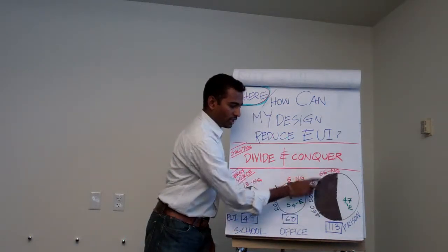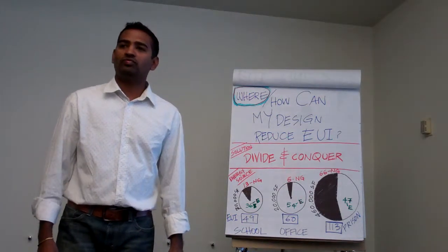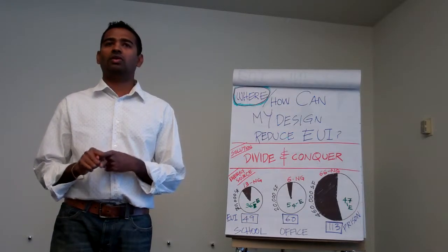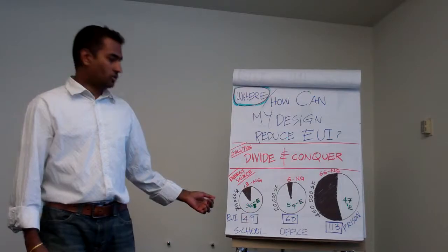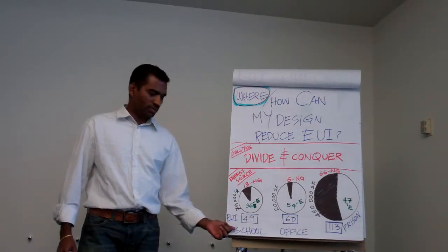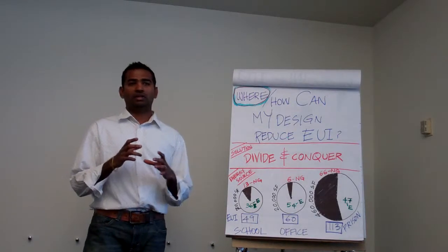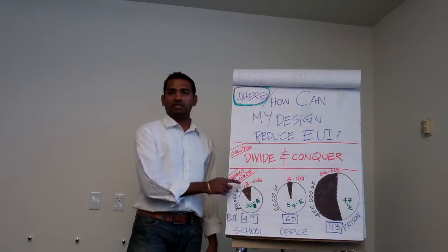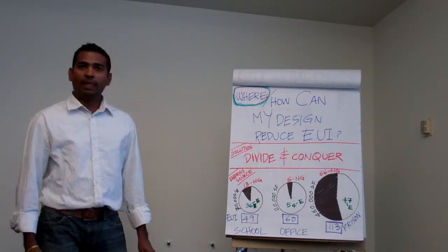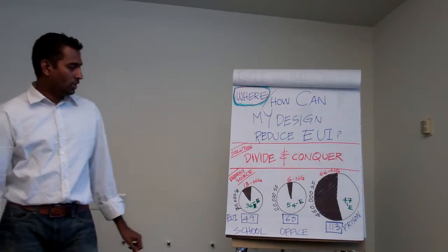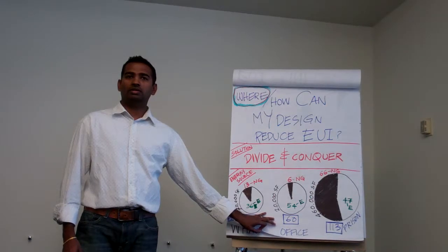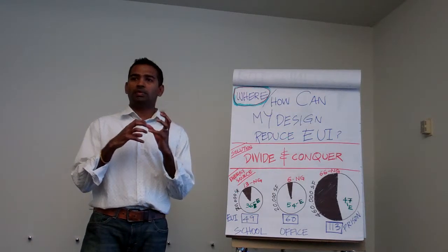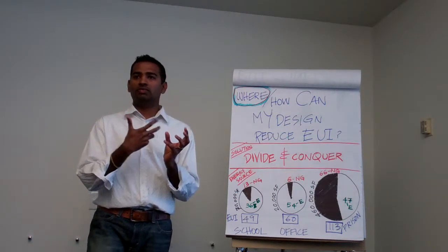But look at this. Why is natural gas a huge consumption in prison? The water heaters usually are gas-fired boilers, and then the kitchen, and then laundry. Yes, because there's a lot of domestic hot water load in a prison as compared to an office or a school. In a school, there is a gymnasium, because this is just for a normal school. It doesn't differentiate between elementary, middle, and high school. But in a typical school, let's say high school, you're going to have shower load, so that's where some of this domestic hot water load is. And the kitchen, kitchens also. So far everyone on the same page? Okay. I think it's important to start breaking these down into simpler portions so we can understand how this will inform design.